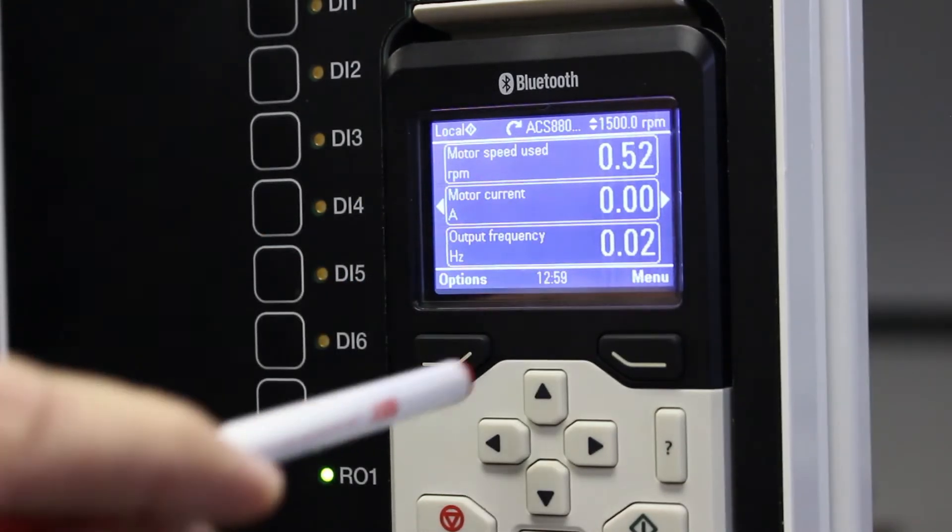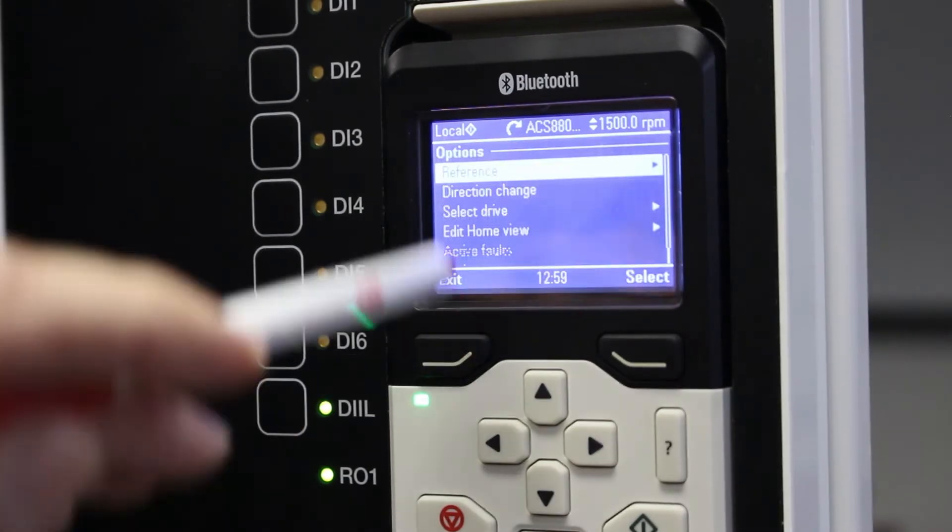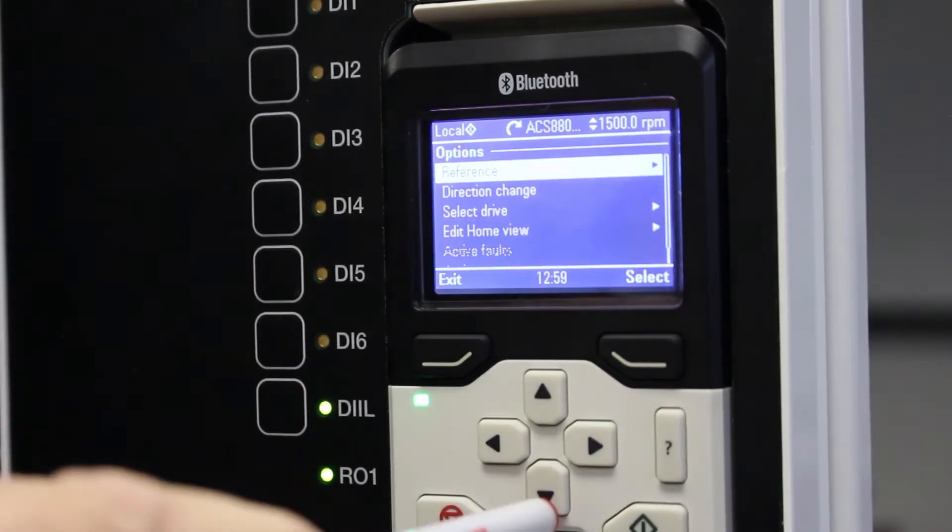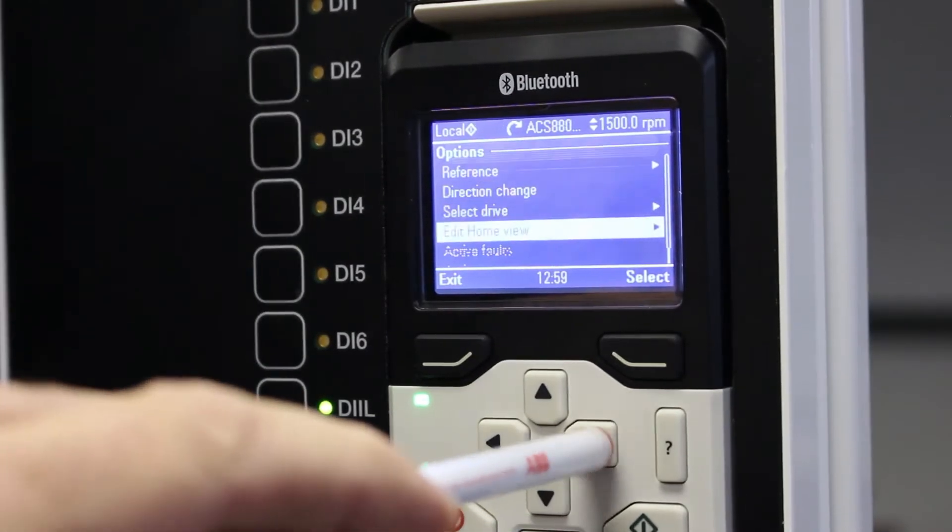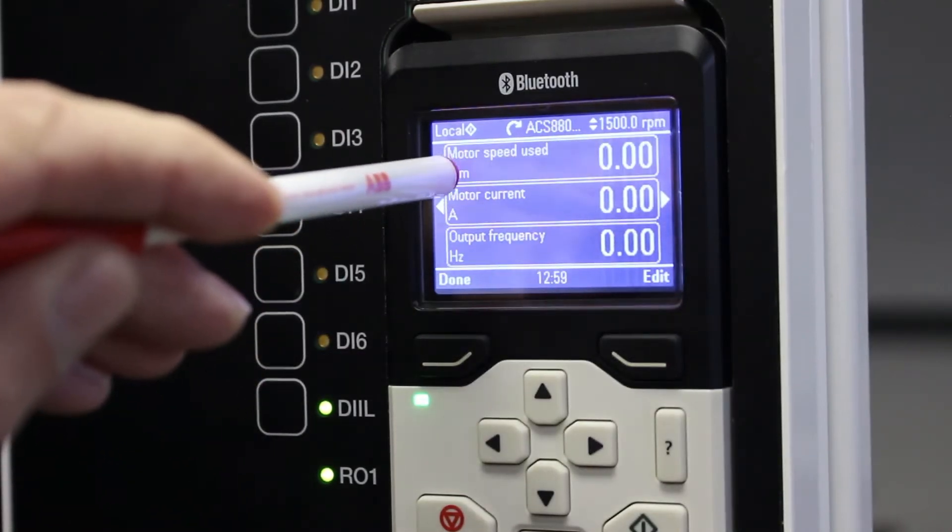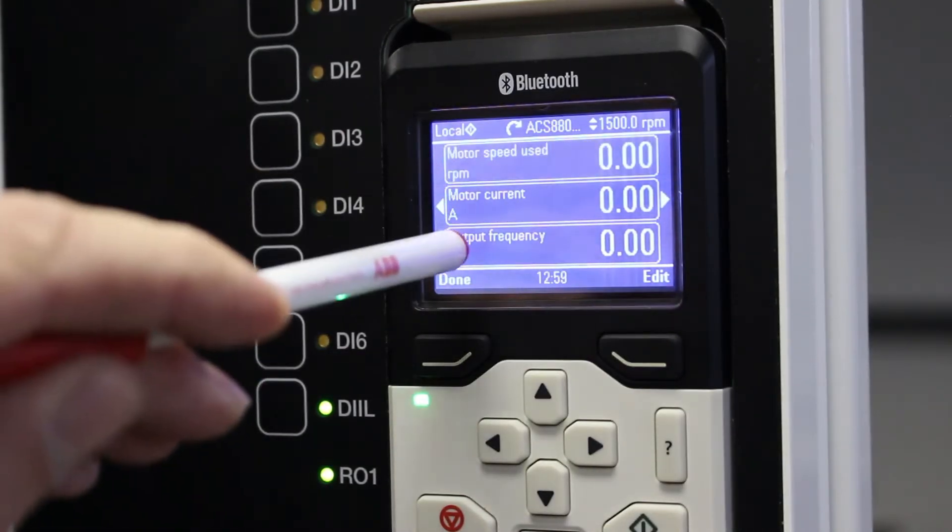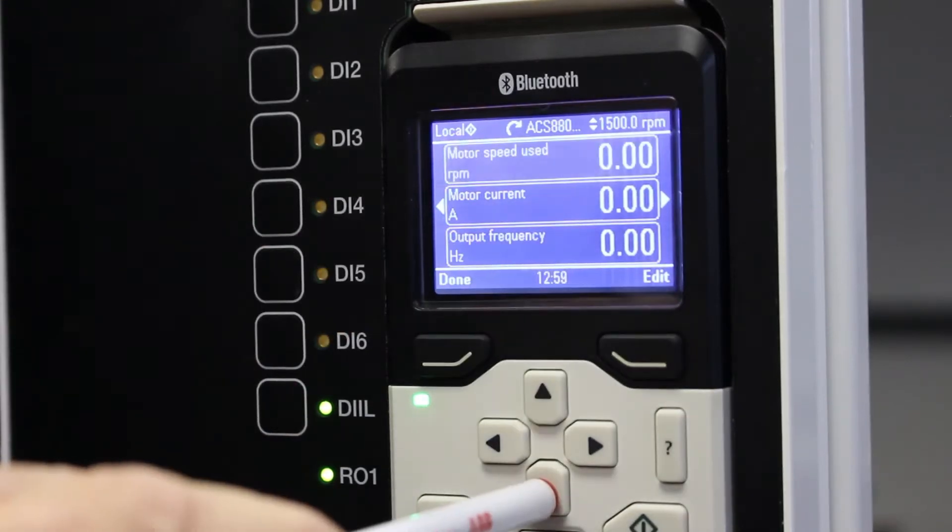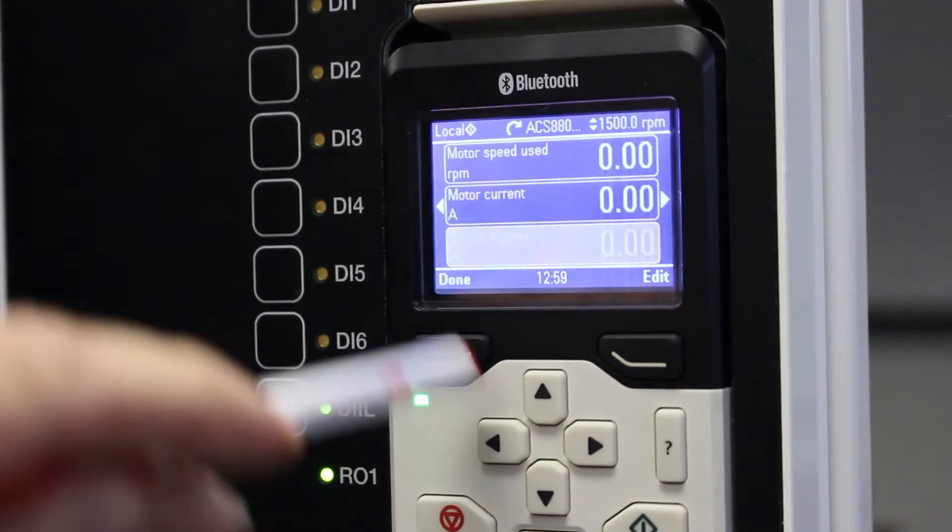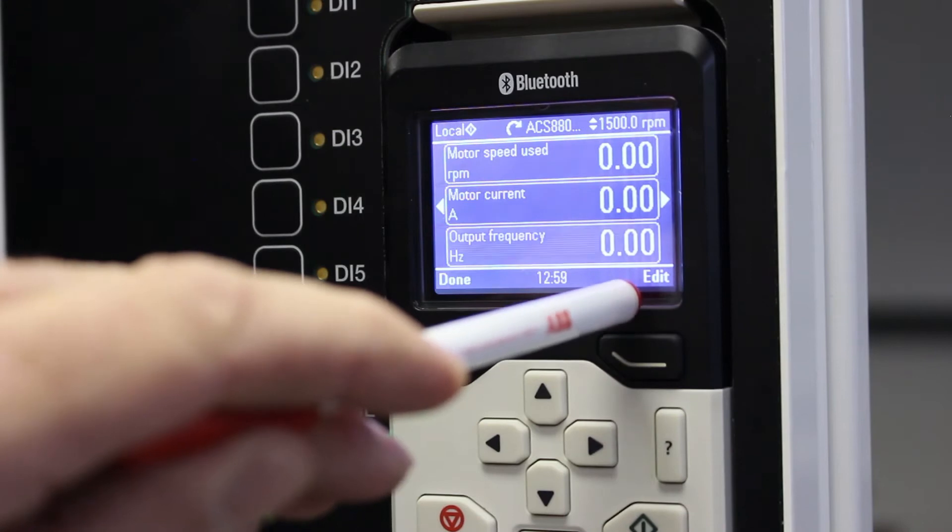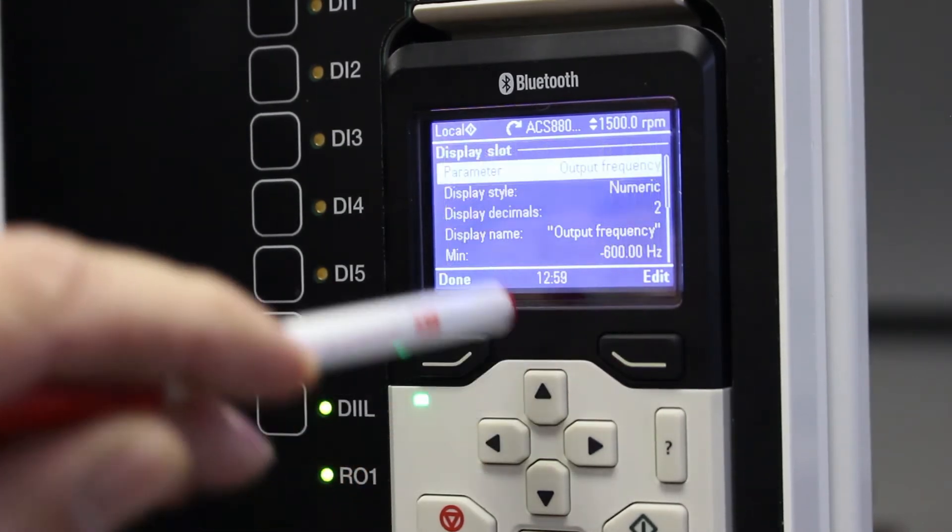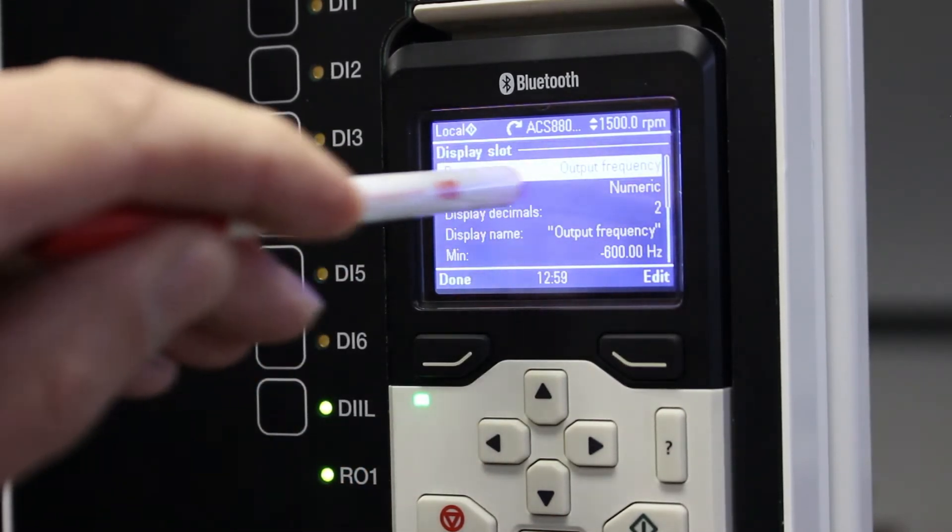Very easy to do. I go to options, scroll down to edit home view and you will see it's now blinking white and black on that position over there but I want to change output frequency. So I scroll down to output frequency and I say edit. Press the edit button, parameter.